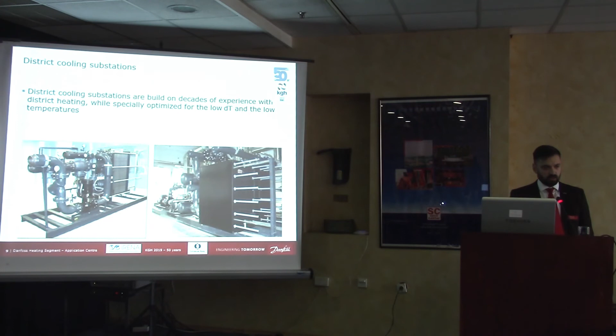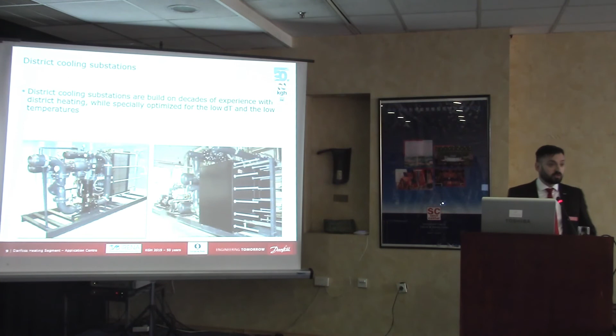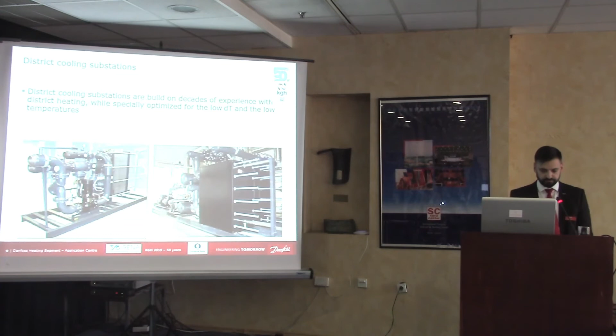Heat exchangers need to be very efficient because the logarithmic mean temperature difference needs to be very small, around one degree. Also, everything is bigger - for the same capacity we need pipes that are 2 or 3 sizes larger in district cooling applications than in district heating.